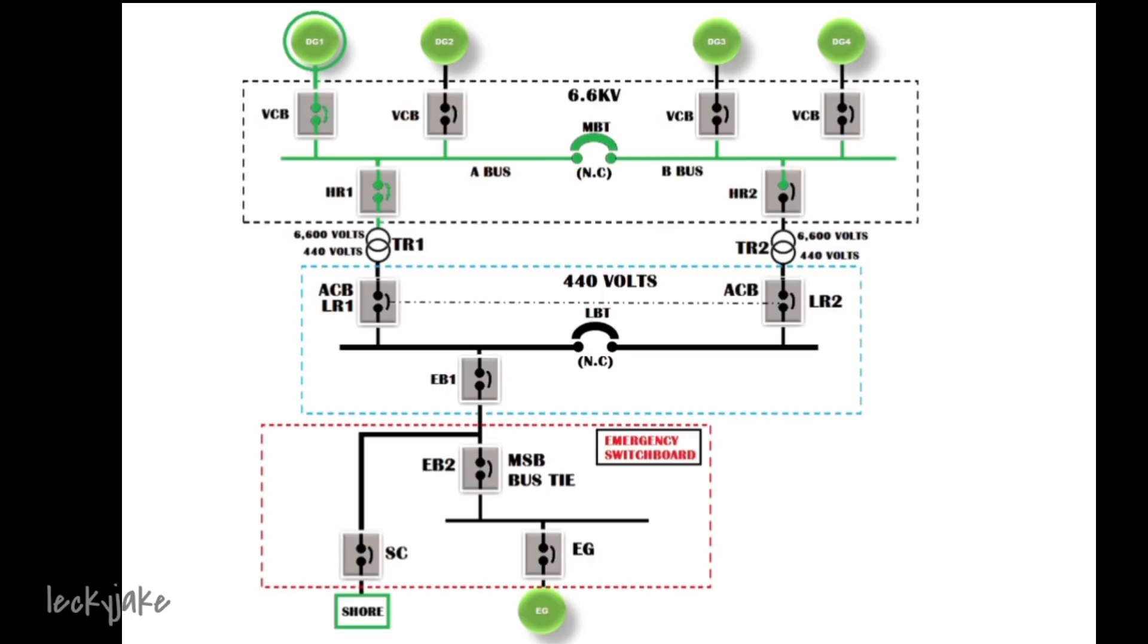Suppose that we decided that transformer number one will be our running transformer, then we need to close the HR1 and we will close the ACB LR1. Take note that the ACB LR1 and HR1 has an interlock with each other. This means that if the LR1 will be opened, then the HR1 will also be opened.